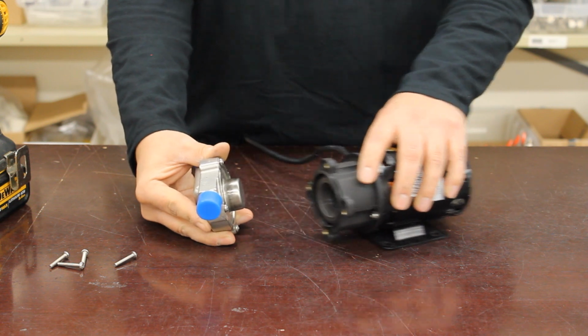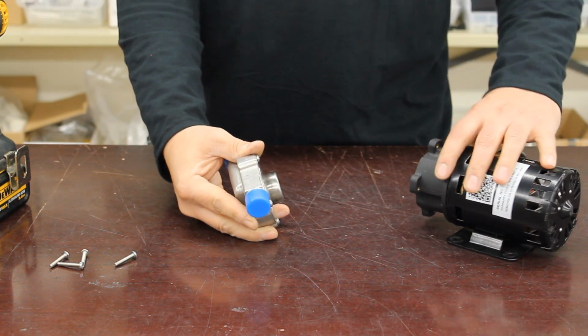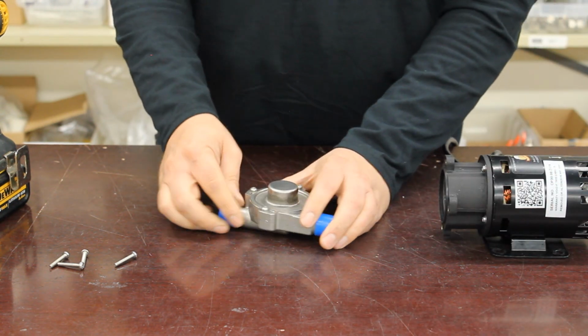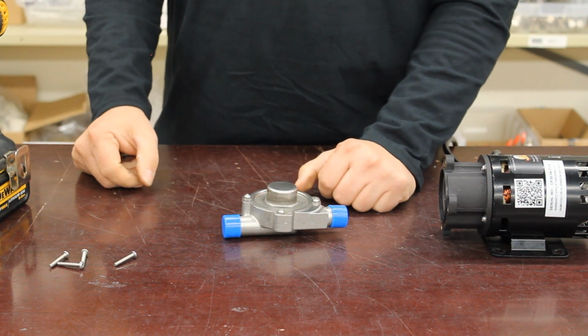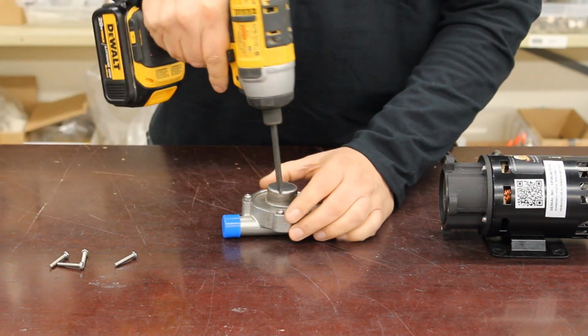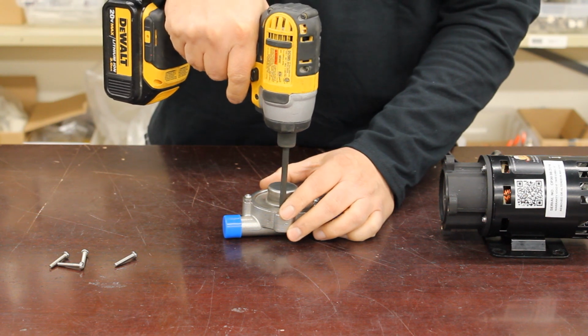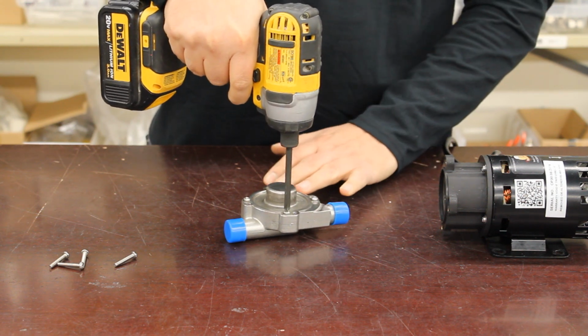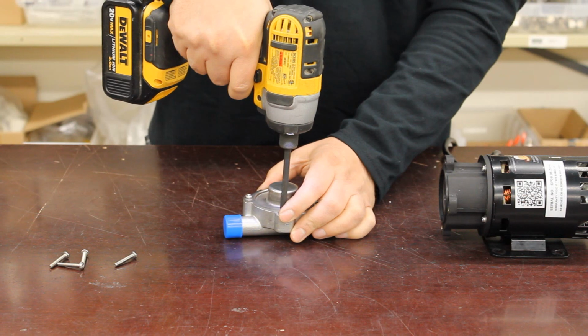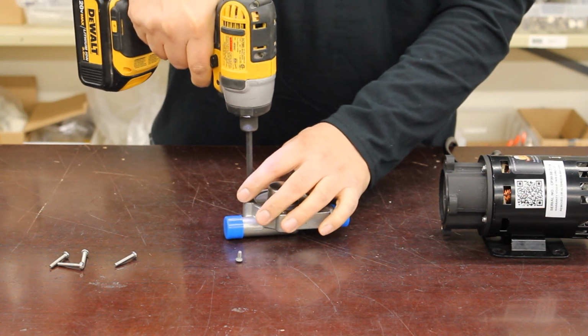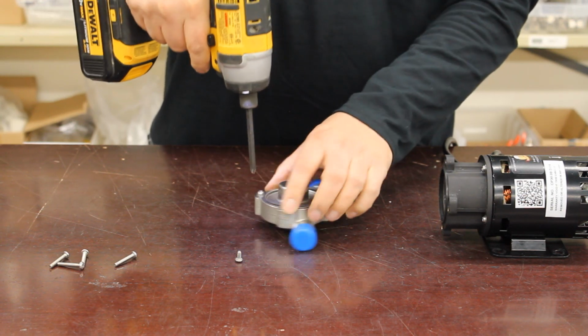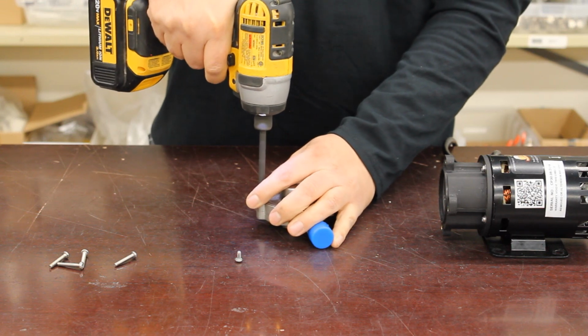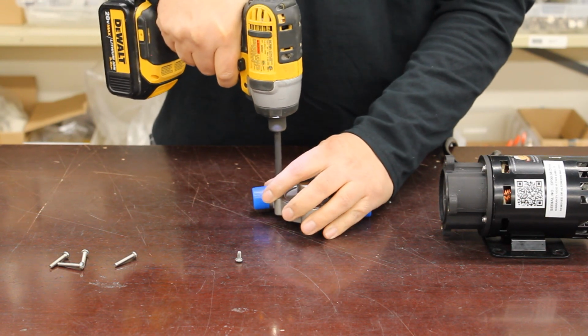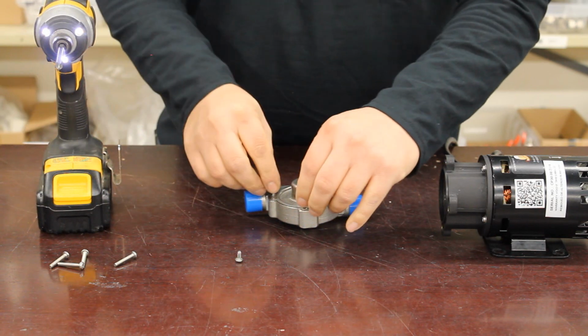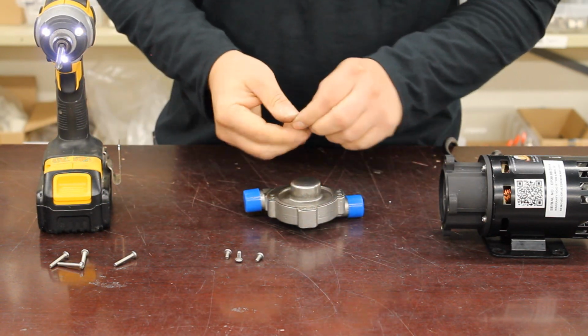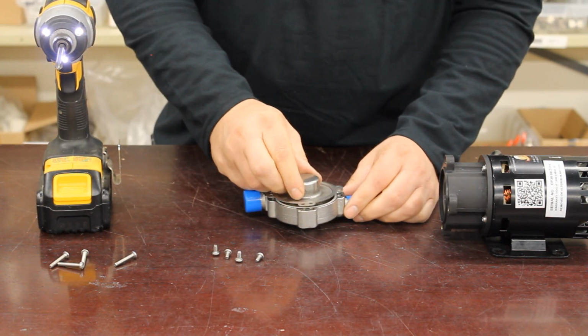So troubleshooting this requires that we take the head off the motor like we've seen before, but now we have to disassemble the head. Now, this is the same step you would take if you had any leaking problems, if you saw water or any liquid leaking out of the head, because this also will expose the seal. So you take these 4 Phillips head screws out of the back plate.